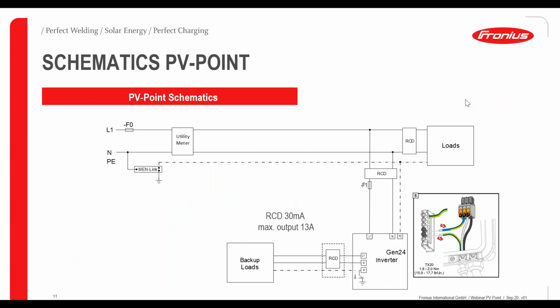There is the schematic showing how it is connected. On the inverter, you have a 3-pole connector, and on this 3-pole connector, you see 2 neutral, 1 phase. All you need to do is go with 1 neutral to the PE terminal, and then you connect the ground cable there. Additionally, you would need an RCD 30 milliamp type A, but no fuse here because there's anyway only a maximum output of 13 amps possible.